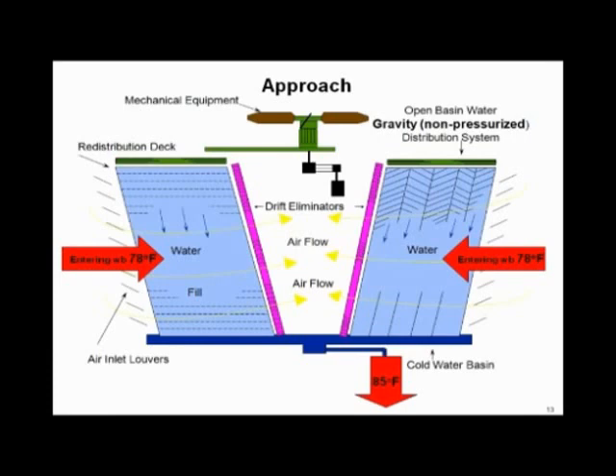I'd evaporate 15 pounds per ton. Wow, throwing something new at you. Not really. I said the nominal tonnage was 15,000 BTUs per ton for a cooling tower ton. So if we get 1,000 BTUs per pound of water, then I have to evaporate 15 pounds of water for every ton in my cooling tower. Simple little thing that you ought to hang on to. It's not exactly 15, but it's so close you can use it and go on.